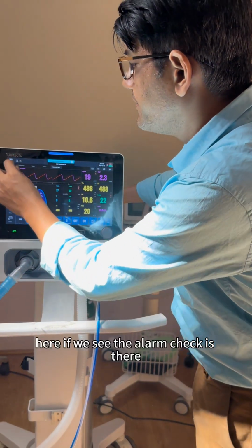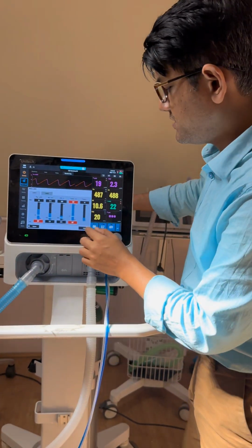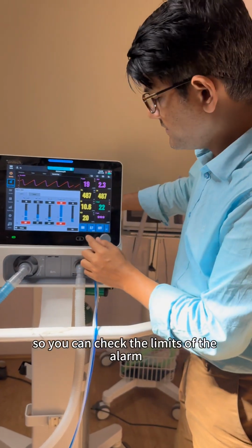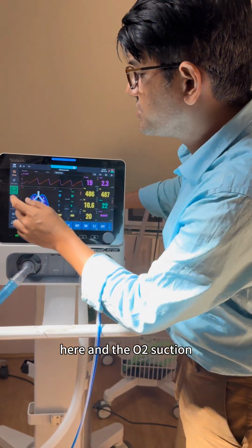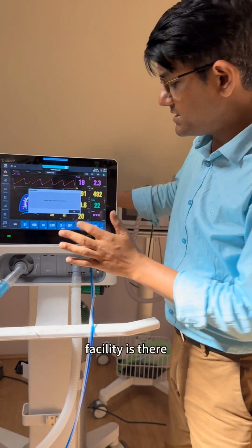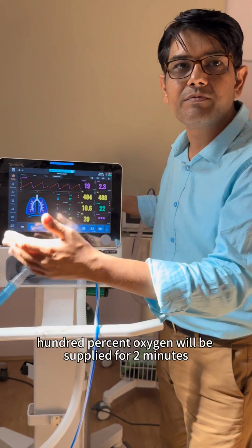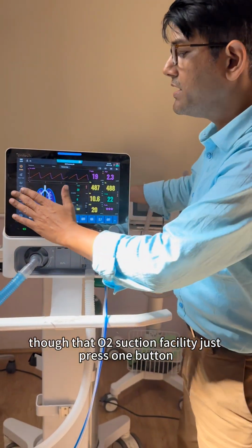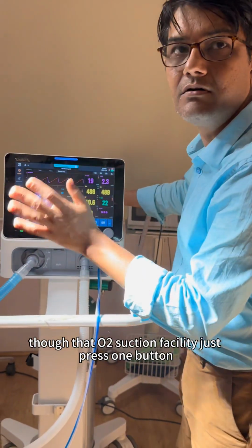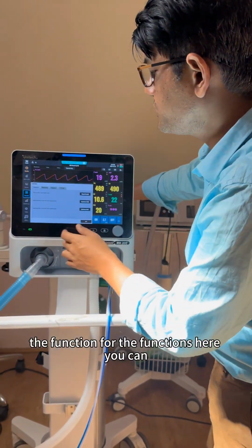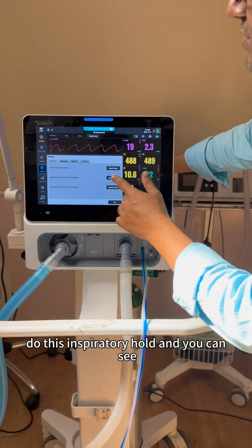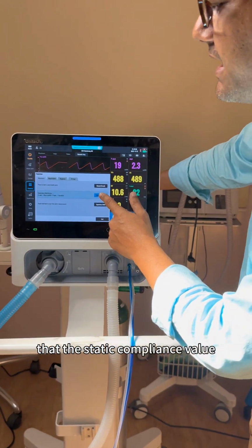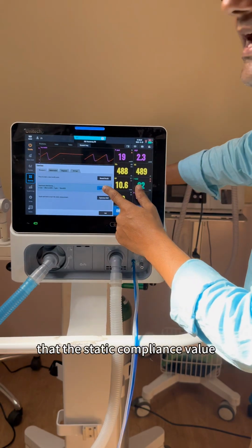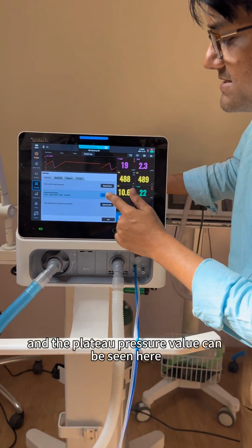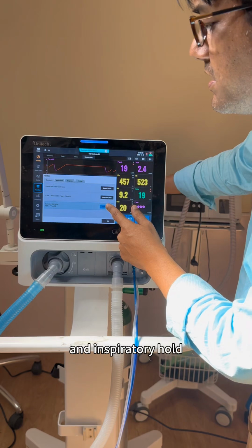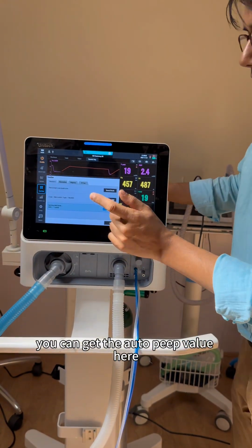And here, if we see, the alarm check is there, so you can check the limits of the alarm here, and the O2 suction is a one-button facility. 100% oxygen will be supplied for 2 minutes, and then it will come back to the normal mode. So just press one button and it's there. For the functions, you can do the inspiratory hold, and you can see the static compliance value and the plateau pressure value here, and with expiratory hold, you can get the auto PEEP value here.